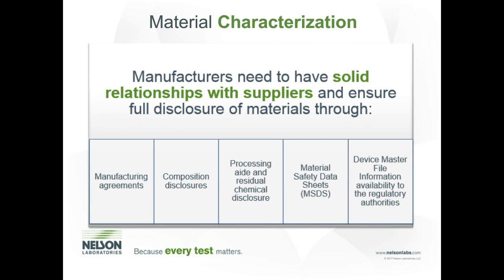And I want to spend just a moment talking about device master files. If you're not sure what a device master file is, let's say I am a manufacturer of raw silicone, and I want to prove to the medical device industry that my silicone is going to be a good, safe material. I do some initial testing, and it may even be the total suite of biocompatibility tests that are required for a certain medical device. I submit those tests to the FDA, and the FDA reviews them. Once they approve of the work done, they give me a master file number for that material. Now I can give you a master file number saying the FDA, well, they don't approve individual materials, but the FDA screened this material and they give me this master file for safety. That is great.